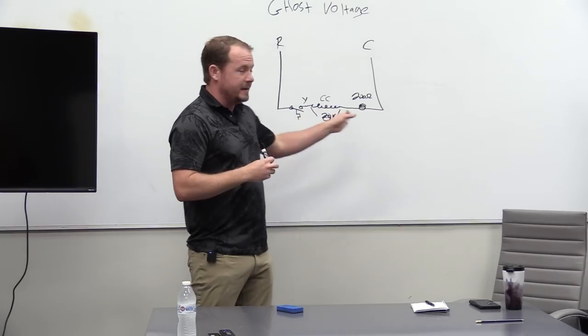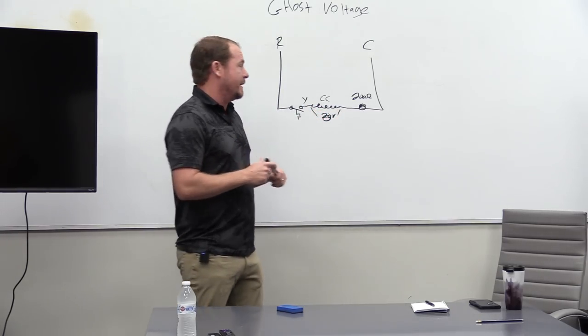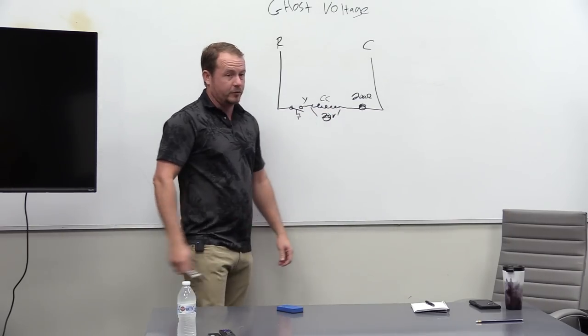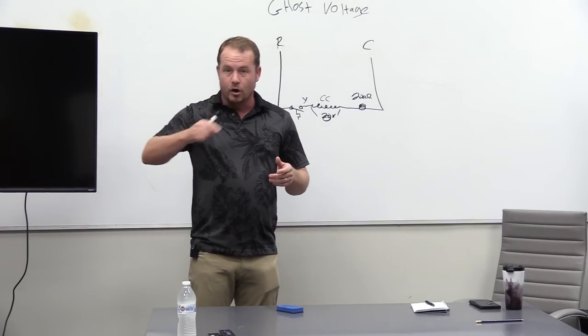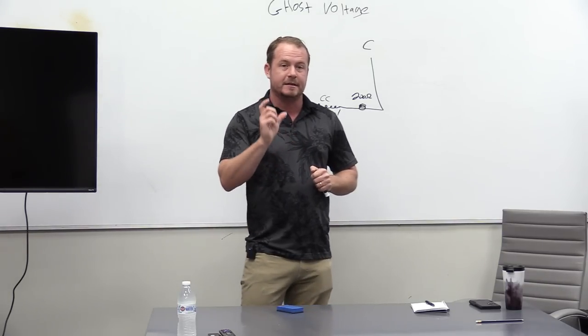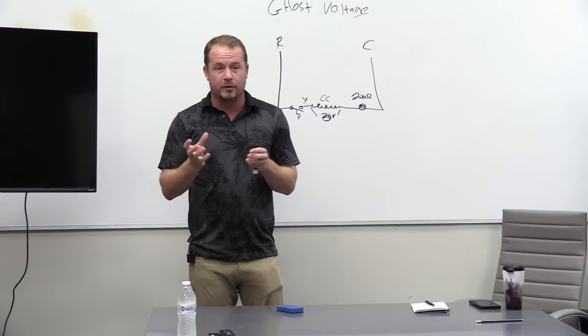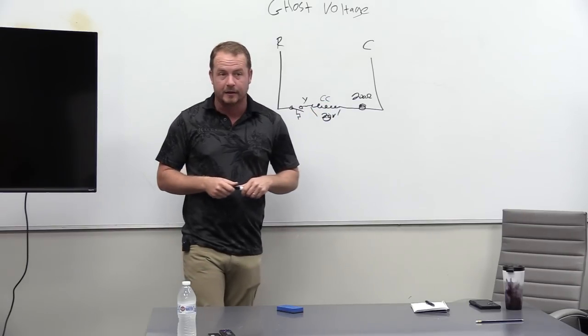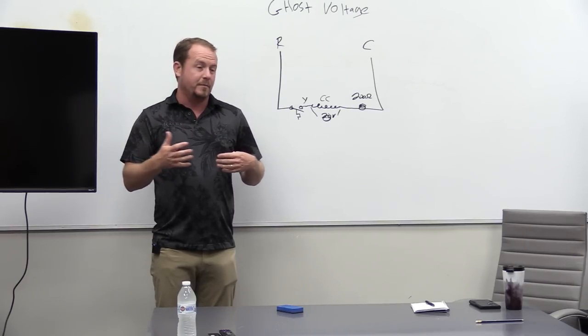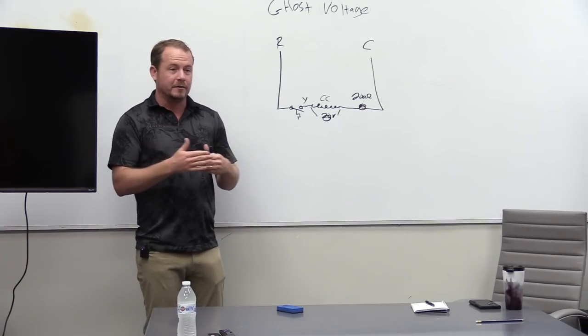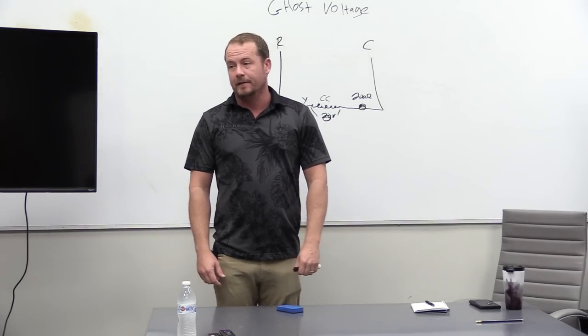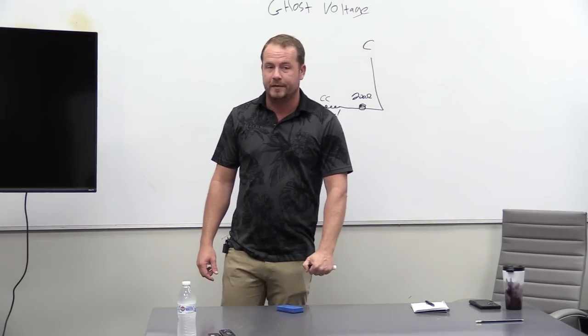If there's no faucets running, there's no pressure, you've got the full pressure, because it's able to make it through and back up, and you see that pressure. But the second that it becomes dynamic and you start to use it, the second that we close this switch and now we energize the contactor, now it disappears on me. There is still going to be flow, there is still going to be motion, but that voltage drop is significant, because the voltage drop exists across another point. And so you're creating another series load. And so the voltage drop exists across the point of highest resistance.